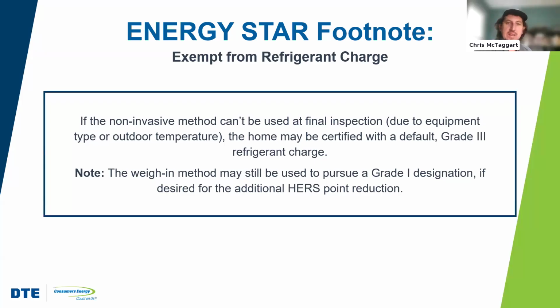And so if you can't use that non-invasive method at final, or maybe you've got standard equipment, but the outdoor conditions are just not right. Let's say you're testing a home in Michigan in wintertime and it just has a standard air conditioner. Well, we're not going to be able to test refrigerant because you can't turn the air conditioner on in the dead of winter. So the home may be certified with a default grade 3 refrigerant charge.